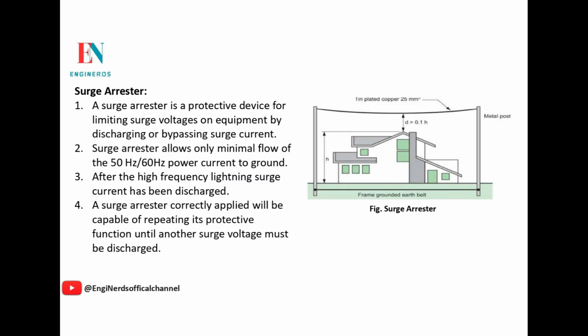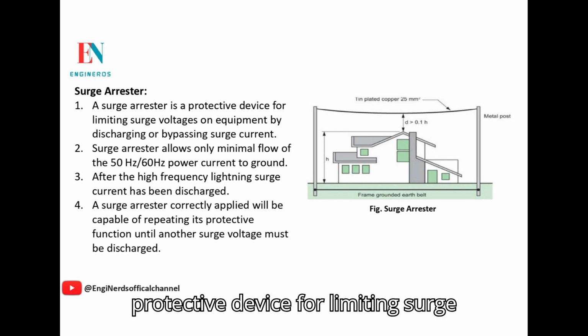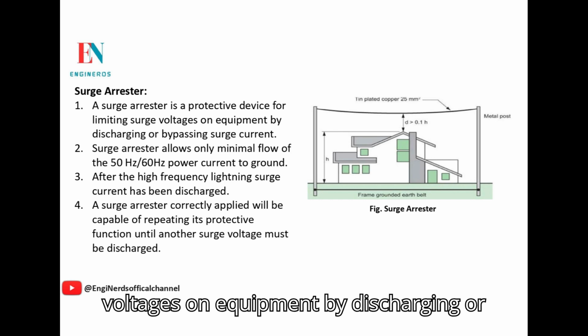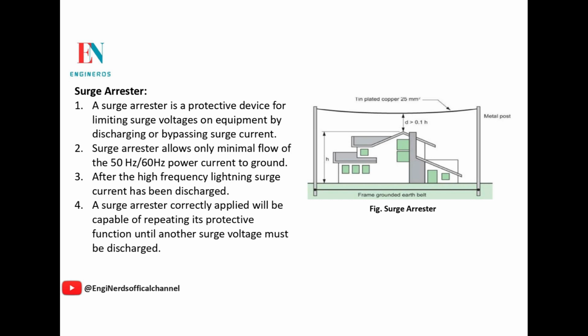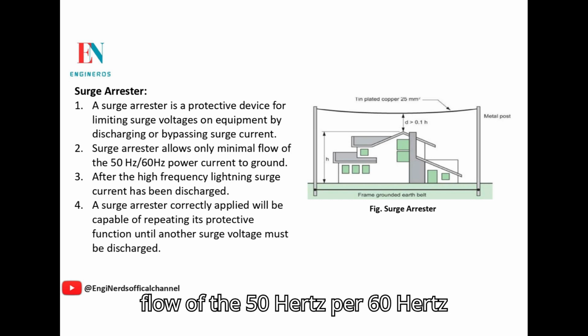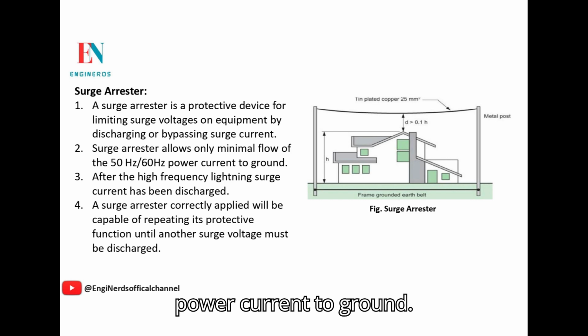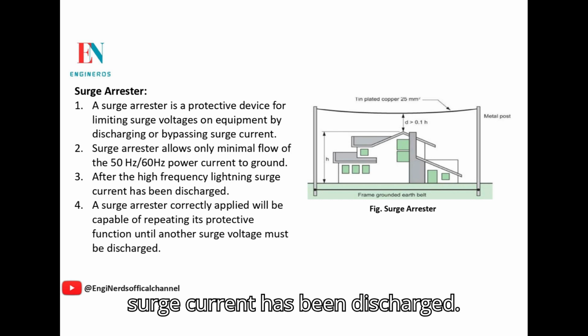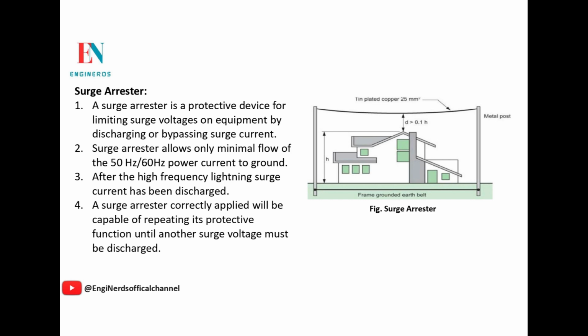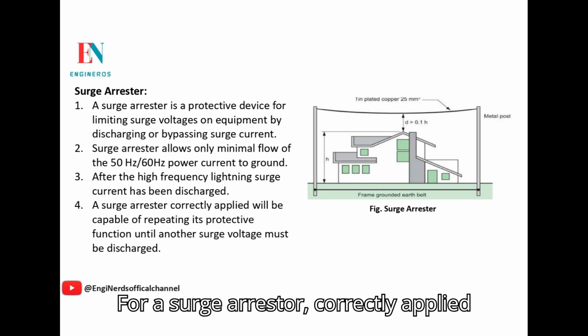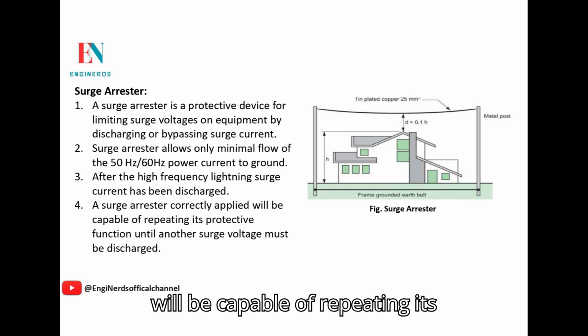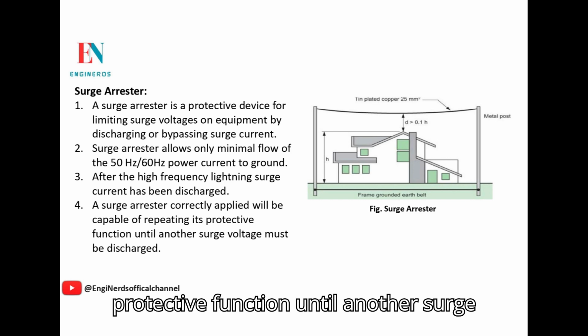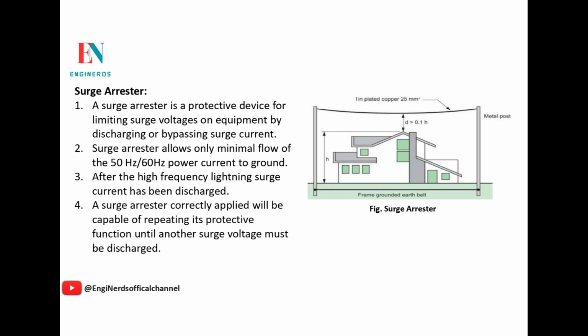Surge arrester. 1. A surge arrester is a protective device for limiting surge voltages on equipment by discharging or bypassing surge current. 2. A surge arrester allows only minimal flow of the 50 Hz or 60 Hz power current to ground after the high-frequency lightning surge current has been discharged. 3. A surge arrester correctly applied will be capable of repeating its protective function until another surge voltage must be discharged.